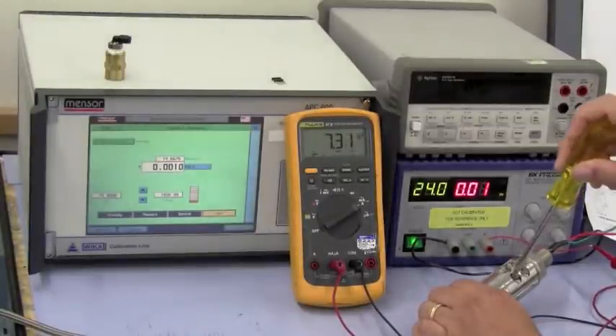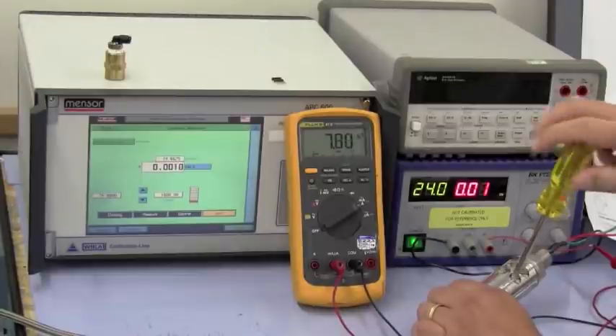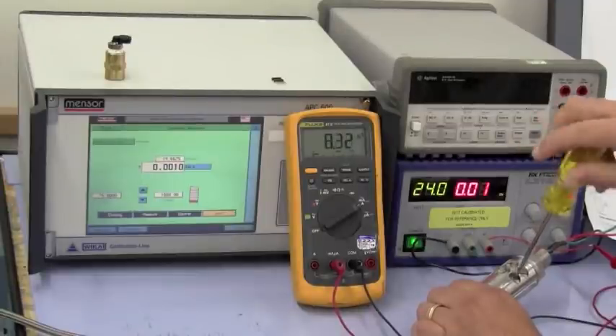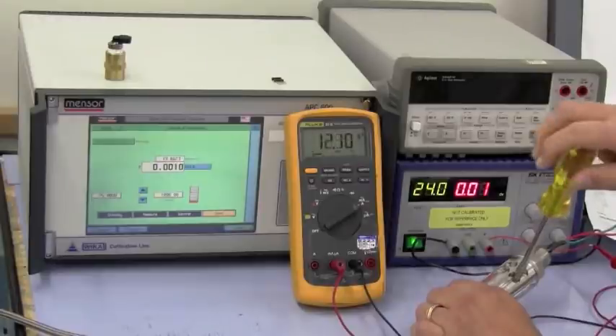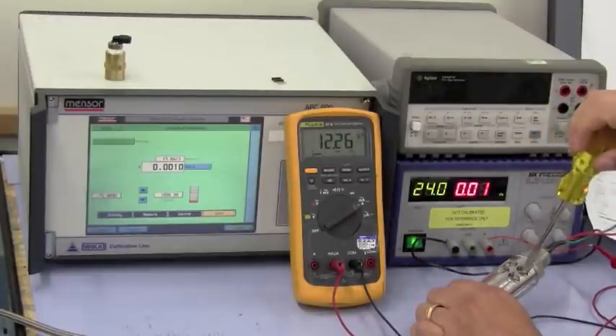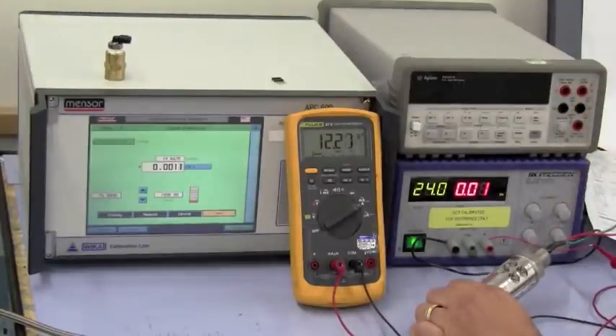And now I'm going to use my screwdriver to adjust the span button until I read 12.20 on the multimeter. And we'll try to get as close as possible using the span. And then we can use the fine span button above in order to fine tune and tweak in the value. And there we are.